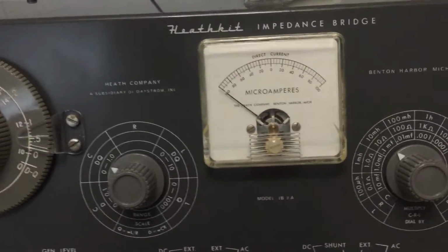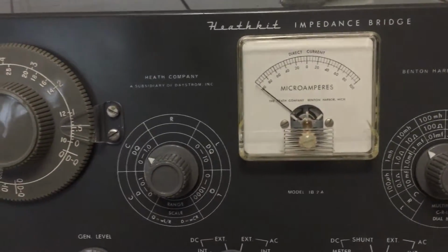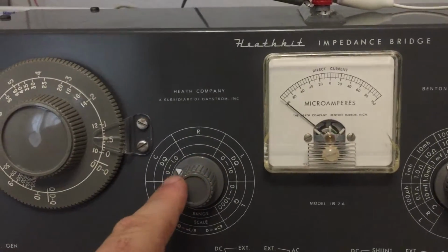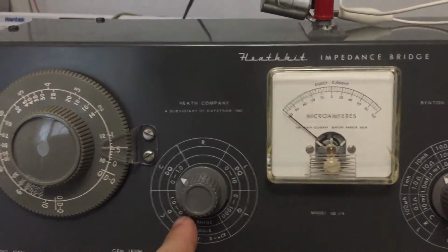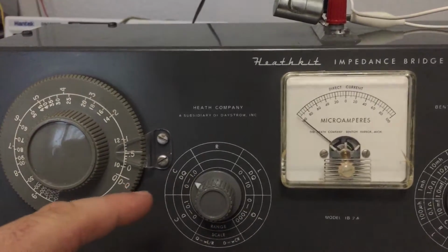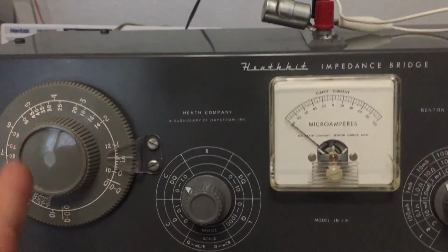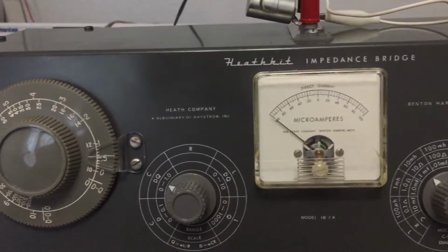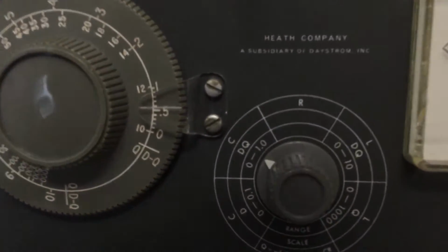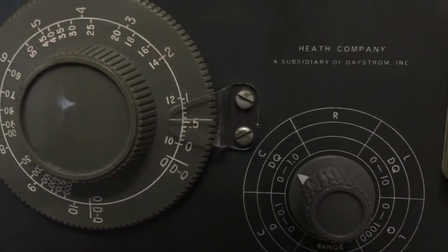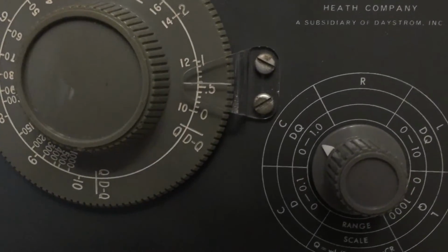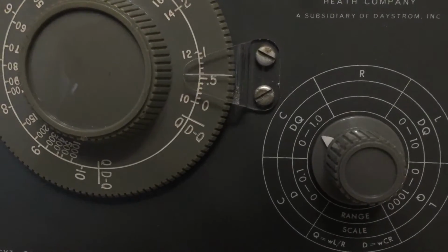So to see if the unit is accurate when going from that conversion to this conversion, because as you know, when you switch to this knob, the 0 to 10 knob turns into a 0 to 1 knob, right? And we'll demonstrate this. So right now we see that we're sitting here at the 0.6, right?